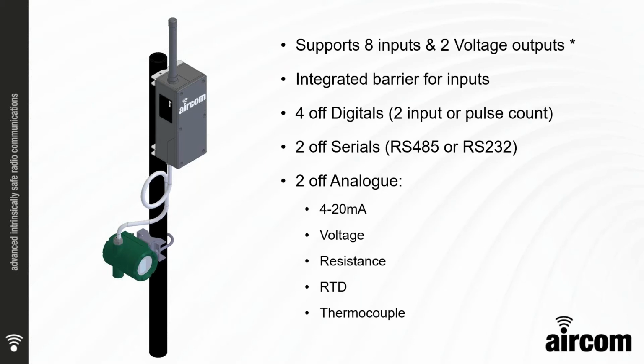The full range of inputs for the standard AIRCOM unit has 8 channels. There are over 32 I/O combinations. For instance, there are 4 digital inputs. 2 of these can be pulse or NAMUR, or all 4 could be simple digital contacts, dry voltage contacts. In addition, there are 2 serial channels utilizing RS485 or RS232, and the data can be both ways, send and receive. There are 2 analog channels, and the analog channels can utilize HART, 4 to 20 milliamp, voltage, resistance, RTD, thermocouple, and others.